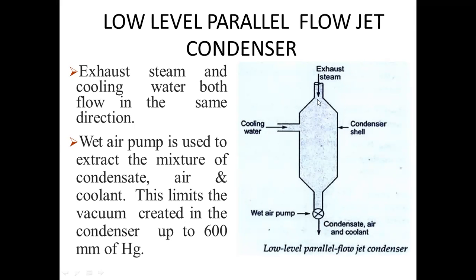Now let's see the low level parallel flow jet condenser. In this case you can see this is a low level parallel flow. Why are we calling it low level? Because this height is very less, you can see. So exhaust steam enters from the top side and cooling water enters from the side wall through the pipe, and inside the condenser they come in contact with each other and get well mixed. After getting mixed, they collect here at the bottom. These can be removed. Exhaust steam and cooling water both flow in the same direction.